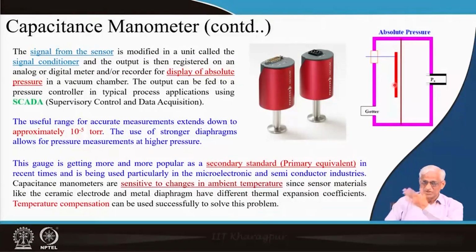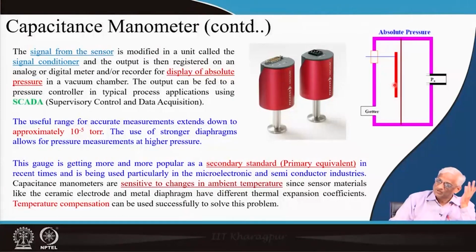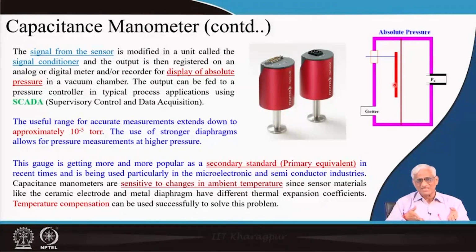We will see when, at some other application time, we are discussing cell phones etc., the role of vacuum there later. Okay. If you do all that, frequency can be measured accurately, and that frequency will be suitably connected through proper converter circuits, and finally, with a little bit of amplifiers you can convert it into a display unit, and the display will start giving the actual pressure. But in the backside what is happening is, first the display is nothing but some converted signal. That signal is proportional to some frequency, that frequency is proportional to capacitance changes, capacitance changes are proportional to deflection changes, which are proportional to the pressure changes, a vacuum range changes from 1000 to 10 power minus 1 millibar across a diaphragm, the other side being perfect vacuum maintained by a getter pump. I am talking a little faster, but you can slowly understand, because these gauges are very popular nowadays.